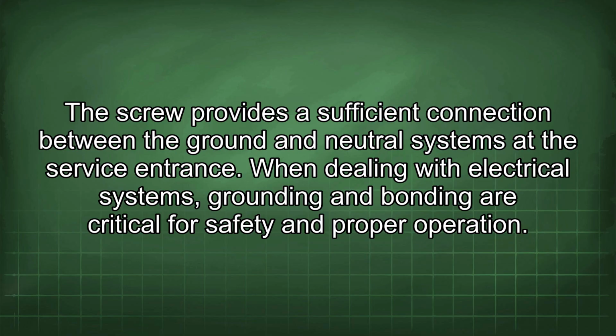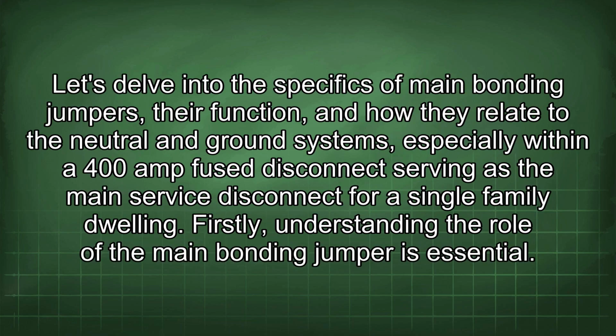When dealing with electrical systems, grounding and bonding are critical for safety and proper operation. Let's delve into the specifics of main bonding jumpers, their function, and how they relate to the neutral and ground systems, especially within a 400 amp fuse disconnect serving as the main service disconnect for a single-family dwelling.